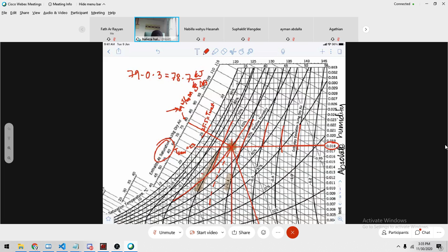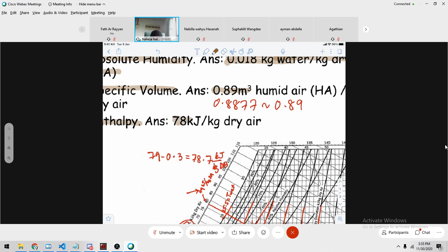So that value that you have over here, 79, is for saturation. But yours is not saturation. So you need to minus that 0.3 from the 79. Your answer will be what? 78.7. Okay, kilojoules per kilogram dry air. If you look at the answer for this solution, it's a bit off, but that's close. It's 78, and we got 78.7.